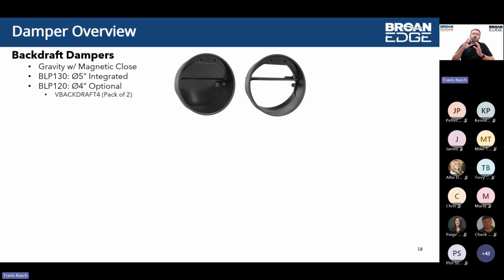And as you can maybe see, there's a top engraved on the damper assemblies. You have the ability to rotate that, depending on what orientation you have it in, maybe it's door up, door down, or on a wall. You have the ability to rotate that damper within that duct assembly or port assembly to the right orientation to make sure that gravity damper falls as we need it to. Again, we have to work with gravity. Gravity's got to be our friend in this case.